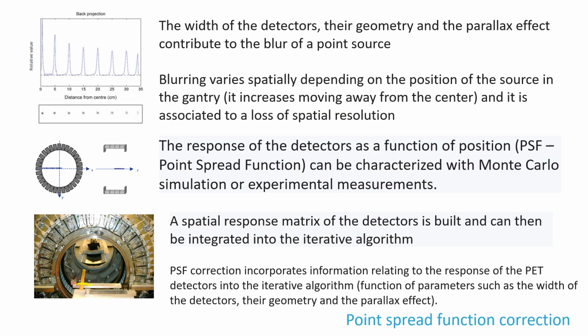The response of the detector as a function of position can be characterized with Monte Carlo simulation or experimental measurements. As a result, a spatial response matrix of the detectors is built and can then be integrated into the iterative algorithm. Over the last decades, PSF reconstruction has become commercially available in clinical PET-CT systems, and these systems have been shown to be more sensitive for the detection of small volume cancer lesions.